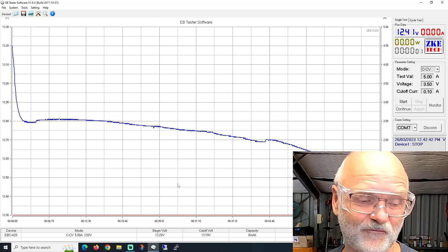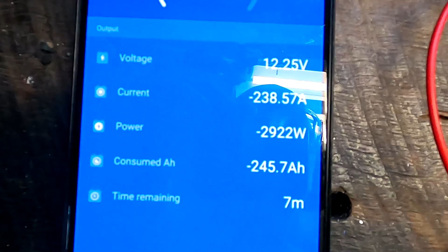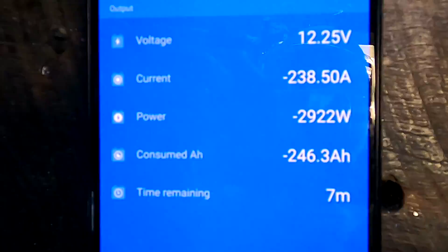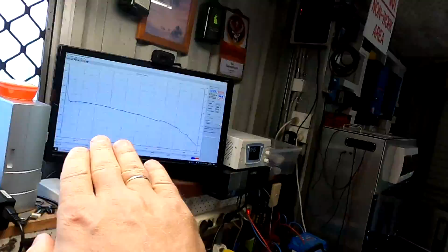Over 1 hour into the test, and we are at 12.4 volts. The BMS claims we are at 0%, and single cell voltages are just above 3.1 volts. The smart shunt has counted 246 ampere hours pulled from these batteries. We're coming to an end now - you can see the curve going down very quickly. There's another 40 ampere hours, maybe 10 minutes maximum, and then we should see a result.